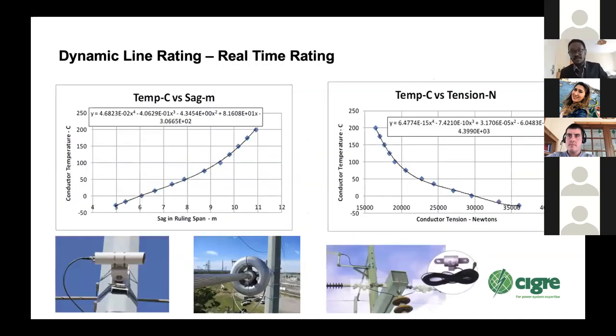The other way of conducting dynamic line rating, which for the purpose of this presentation we'll call the real-time rating, involves the use of sensors. So sensors are placed on the line, and they're used to measure the temperature of the line, the sag of the line, or the tension along the line. And using this information, we could determine what the weather conditions actually are on the line, because we have the CIGRE standards, and we can fall back to our calculations. There are several advantages of using actual sensors. For example, it usually provides a more accurate picture of the conditions along the line.